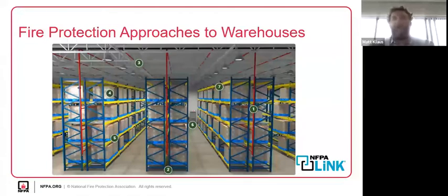One, when a fire occurs in the rack, we've got to allow space for the hot gases coming off the fire to rise up near the sprinkler, which will control that fire and, hopefully in some cases, suppress it, depending on the mode we pick. But we've got to leave that space free and clear.